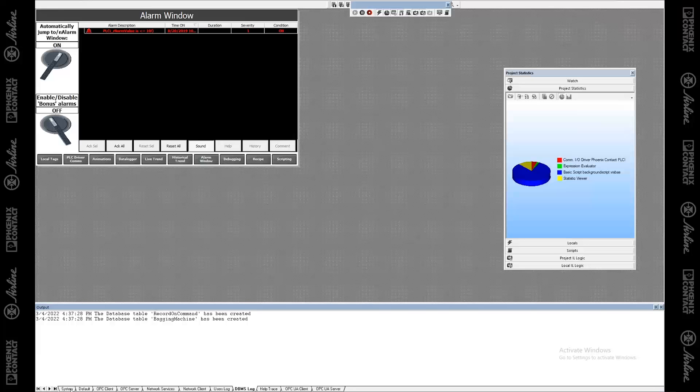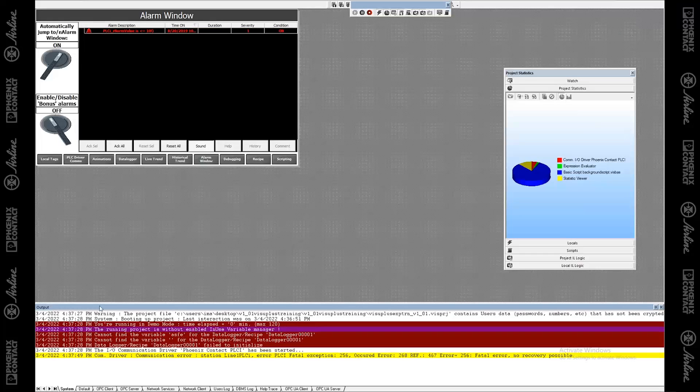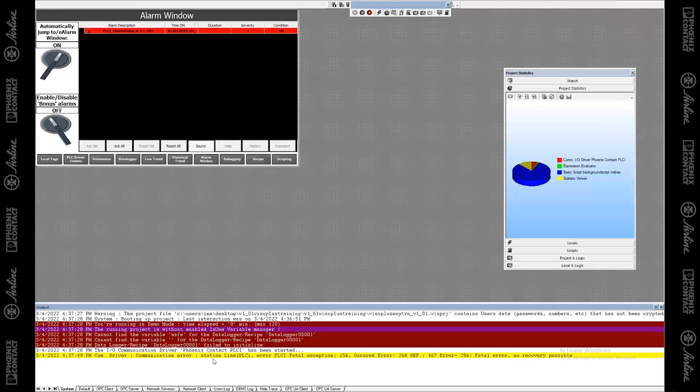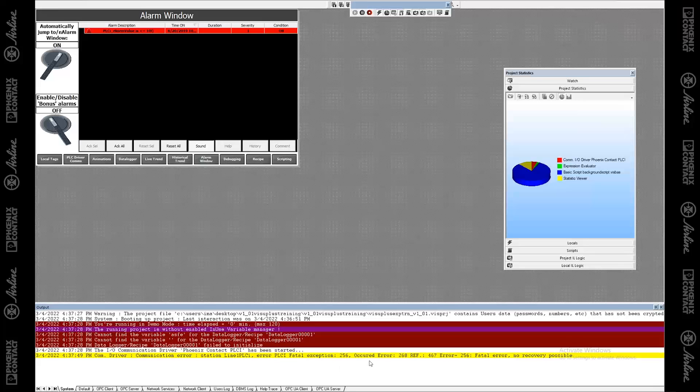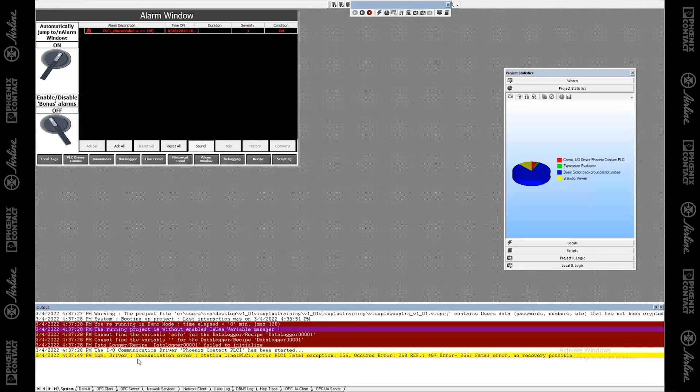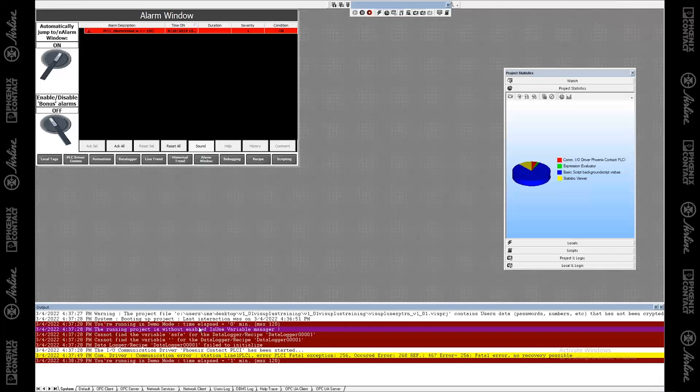So you can see details about your database management and your recipes and databases. And it's telling you, I just created these two database tables. And if under system, this is the most common one where I'm almost always looking at the system, you can find general information like, I'm starting, I'm launching this driver. And I've got this driver communication error. This makes sense because I'm not connected up to my PLC. So it's having a communication error. It can't reach it. So all my PLC tags aren't going to be updating. Since I'm in demo mode, with the simulation, you're allowed to run it for, I guess, two hours, it looks like.